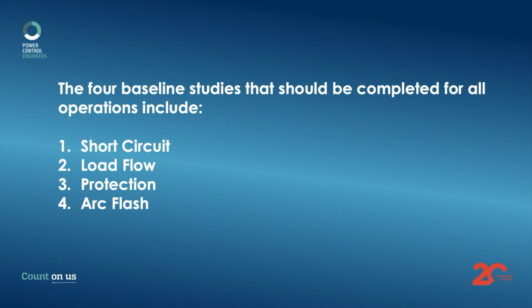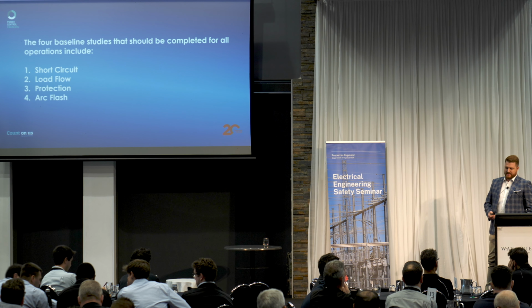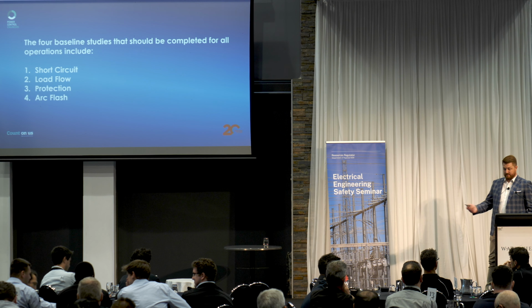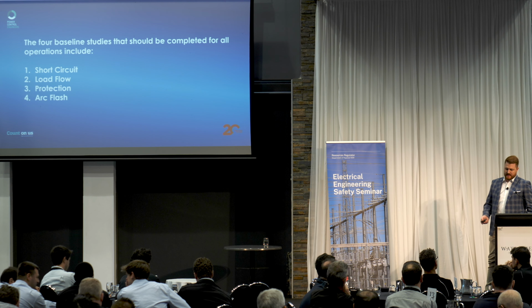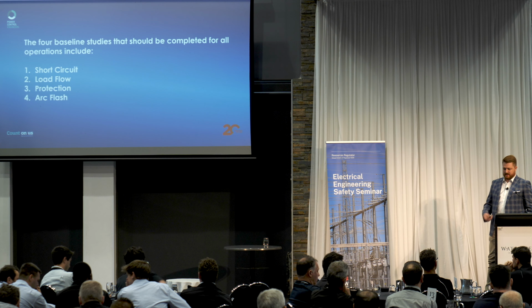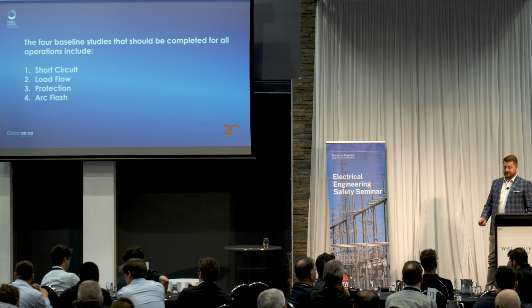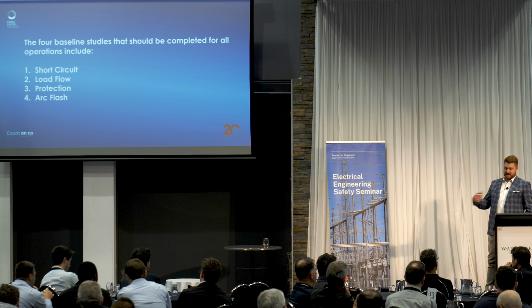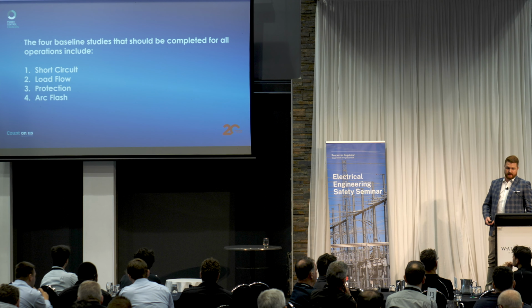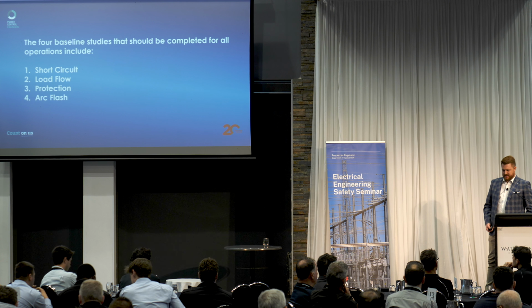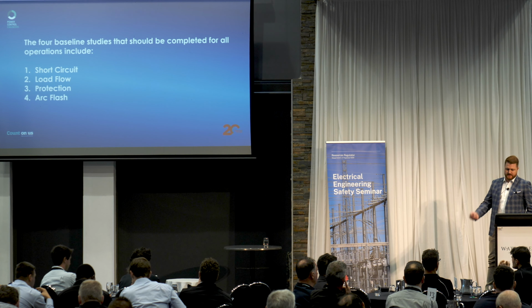Step 2, run studies. So correctly calculate system parameters based on realistic study scenarios. The 4 baseline studies that should be done for all operations at a minimum include short circuit studies, load flow studies, protection and arc flash, which depending on the nature of your operation can be extended to include further studies such as harmonics and power quality. And really, the amount of power system studies that can be done, there's a lot out there, depending on the complexity of your system.